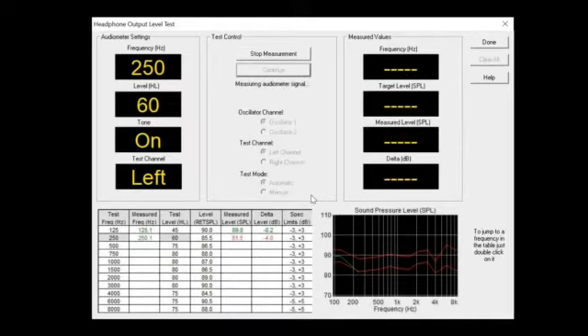Now, we're 4 dB off. It's going to compensate for that 4 dB and recalibrate the audio. Oh, I must have moved the headphone a little bit. Well, it's off 7 dB. It's brought it up to there. So that calibration now is in the system.